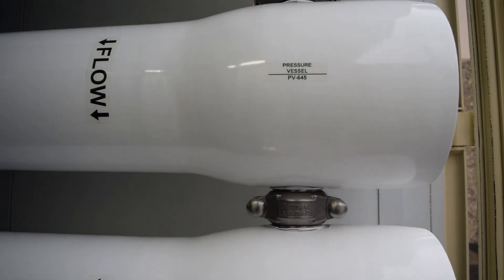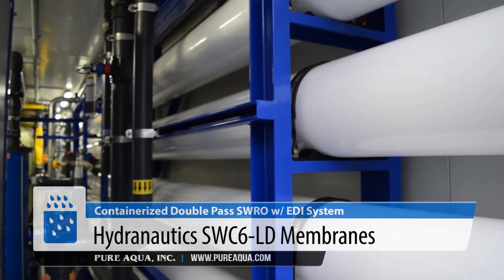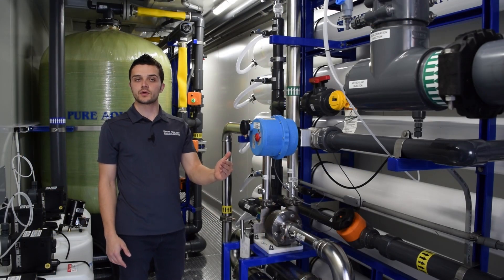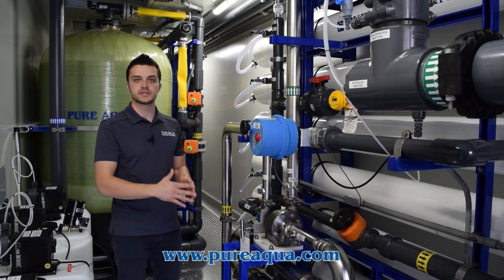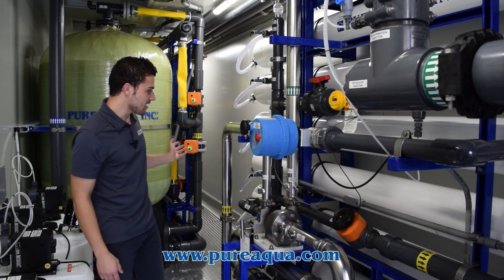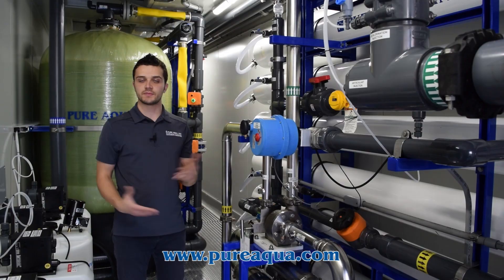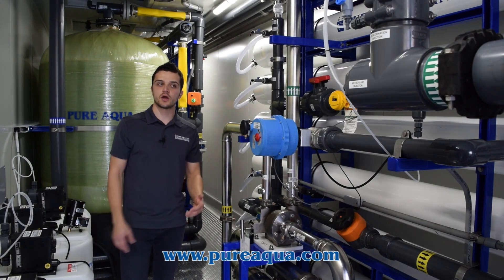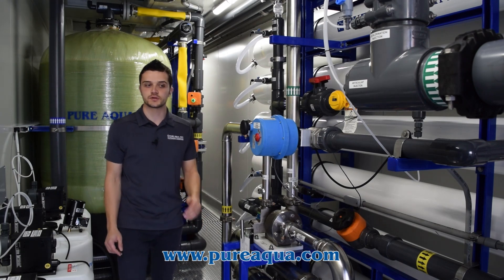We're utilizing Hydranautics' SWC6-LD membrane, which allows us to operate in this wide range of temperatures and pressures. It maintains the water quality required downstream while maintaining a low enough pressure that we can use the same pump and same setup across this wide range. Furthermore, we have a permeate flush where the system and membranes get flushed every four hours or every shutdown. That helps preserve the membranes longer and wash off any small particles stuck on the membrane surface.